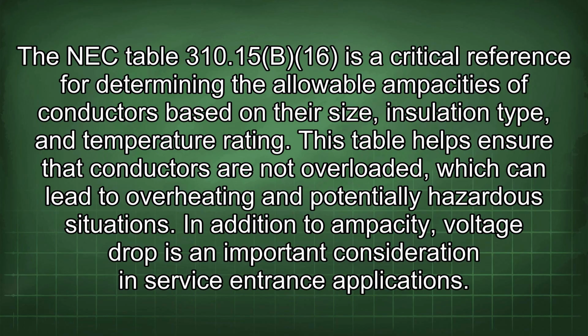The NEC Table 310.15(B)(16) is a critical reference for determining the allowable ampacities of conductors based on their size, insulation type, and temperature rating. This table helps ensure that conductors are not overloaded, which can lead to overheating and potentially hazardous situations.